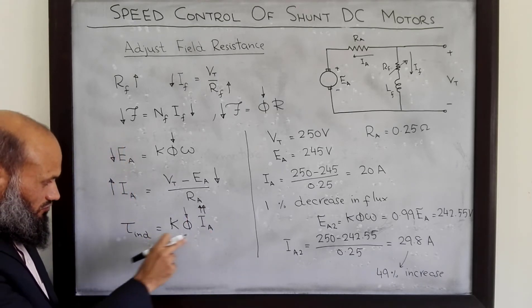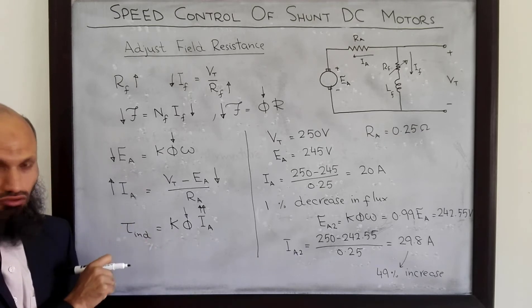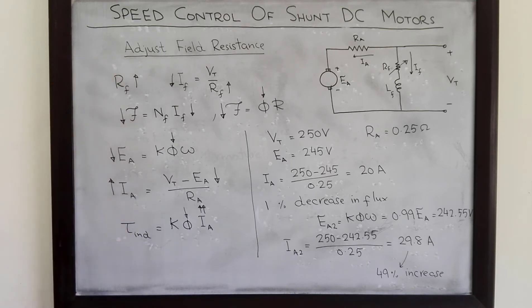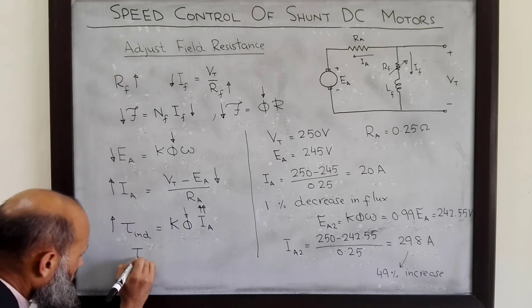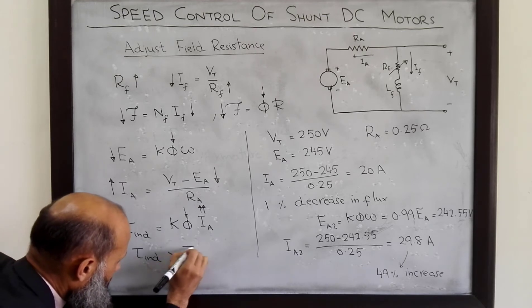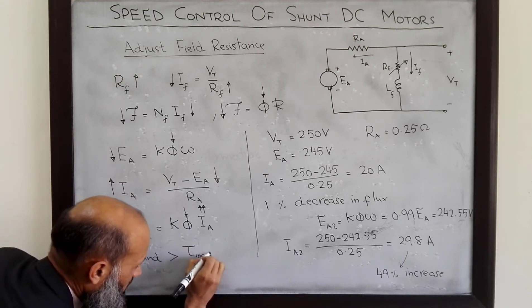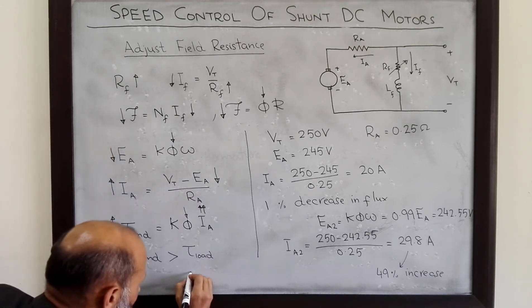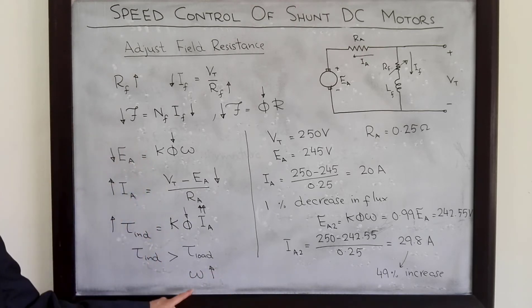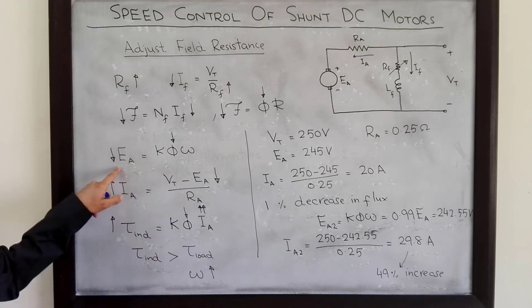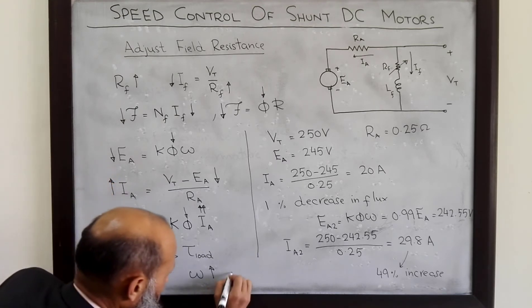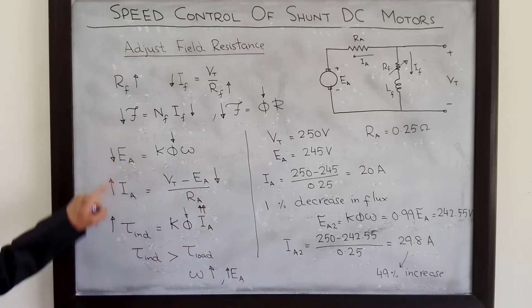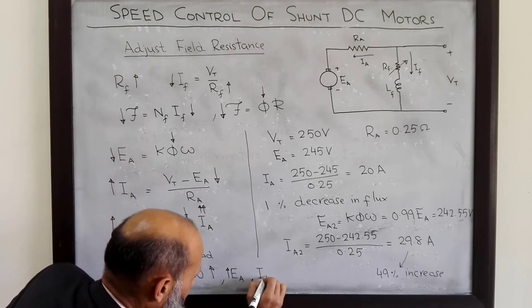In the expression for induced torque, if there is a decrease in flux, there is a large increase in armature current, so the net effect is an increase in induced torque. When the field resistor is increased, induced torque will also increase and become larger than the load torque, so the motor will gain speed. An increase in ω will then result in an increase in EA.